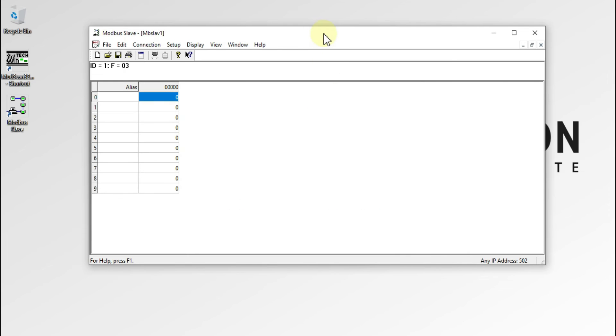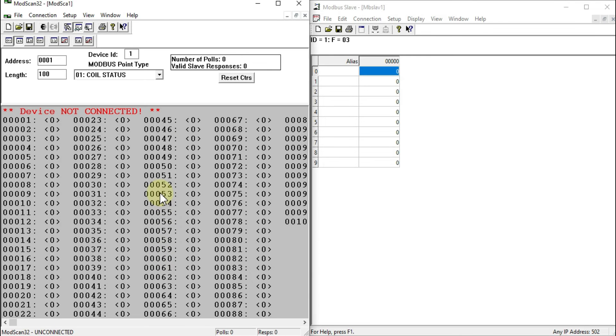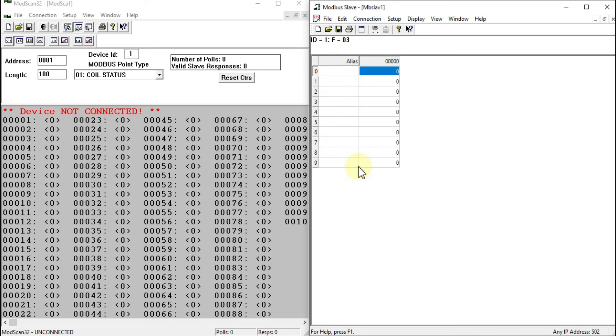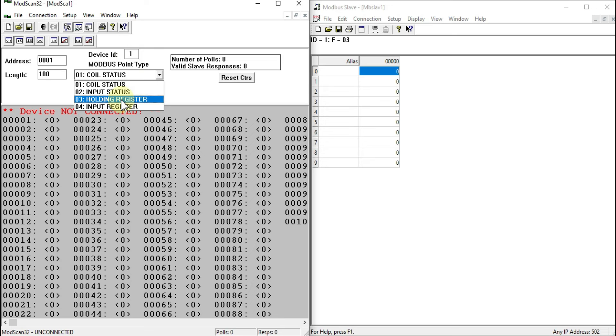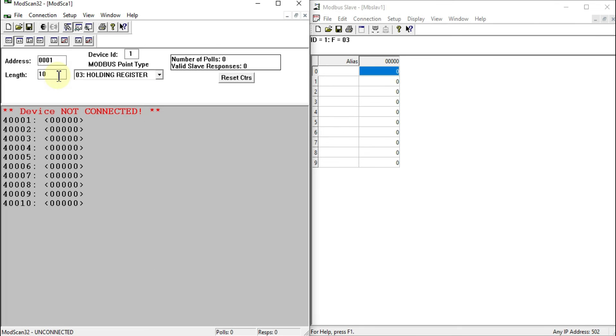Now I want to test this server, so I'll open ModScan32. The Modbus Slave software is running the Modbus TCP server with function code 3 (holding registers), 10 holding registers, and slave ID 1. In ModScan32, enter slave ID 1, select holding register instead of coil status, and reduce the length from 100 to 10 to match the server configuration.